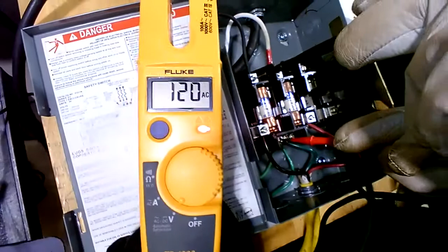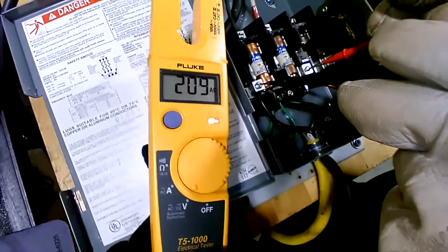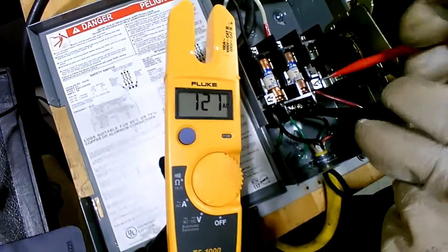208. Now, check each one of those to ground. So he's going from ground. If you can move your hand over. All right. Now he's checking from each incoming leg to ground. 120. Now move to the other one. 120. That's correct. Now do the same thing on the bottom, leaving the fuses. You're going to check both L1 and L2. You got your 208, and now check from each one to ground. And they're 120 apiece to ground.